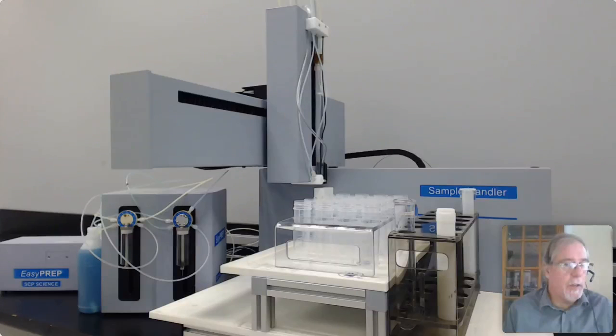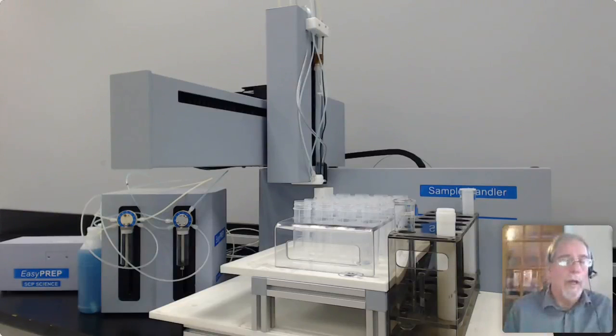Today's configuration is with the dual pumps, the 25 ml syringes to dispense the liquid. So your acid would be connected to one of the ports. Then we dispense through PFA dispensing tubes. We use either a 0.4 millimeter or a 1.0 millimeter ID for the dispensing tips. Today, when you see blue liquid dispensing, that'll represent nitric acid. If you see yellow liquid being dispensed, that represents hydrochloric acid.